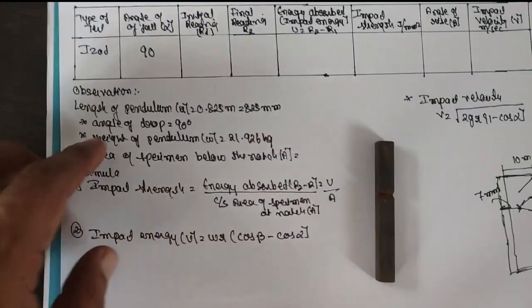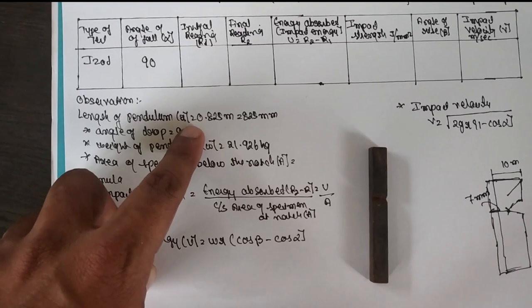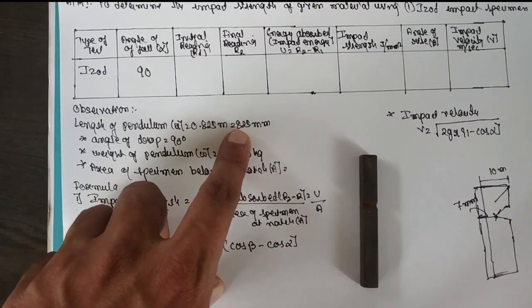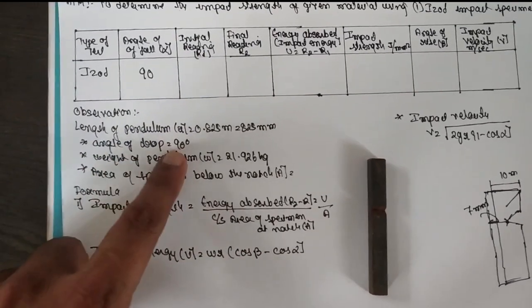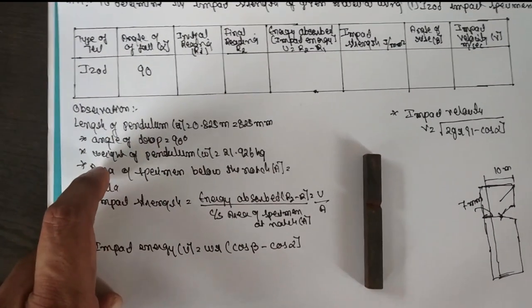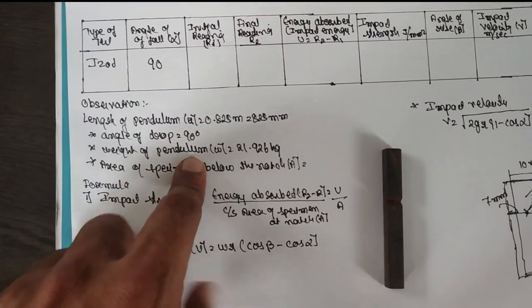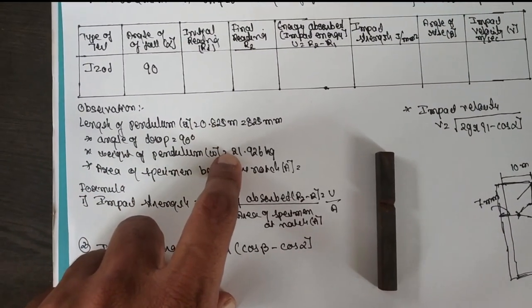The observation contains the length of the pendulum at 0.825 meters. In terms of millimeters, it is 825 mm. Angle of drop is 90 degrees because it is IZOD. In case of Charpy, it should be 140. The weight of the pendulum is 21.926 kg.